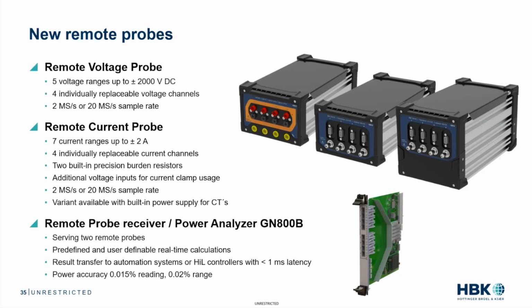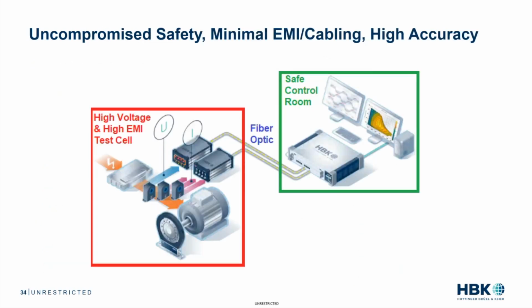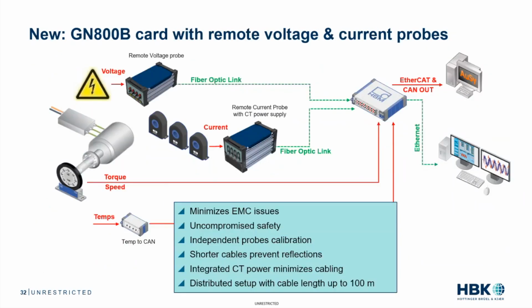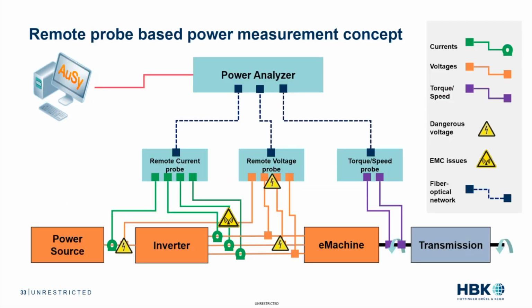The fiber optic signals coming out of these remote probes would then connect to this remote probe receiver, which is actually embedded. You basically slide one of these into your mainframe. If you want to make more voltage and current measurements, you just add more probes and more of these receiver cards. Basically, you have a power accuracy of 0.015% of reading and 0.02% of range. And so this is really going to provide you with a lot more safety. And as we mentioned back here, it mitigates your EMI issues, provides you with shorter cables, and minimizes cabling. And you're going to be able to calibrate your probes a lot more easily without having to send back the mainframe.